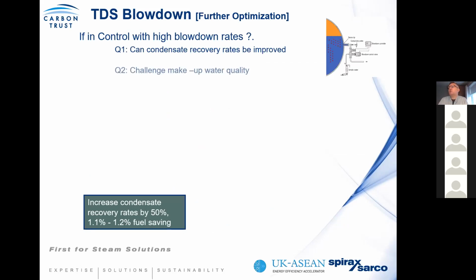Challenge makeup water quality. Just because you have soft water doesn't mean it's the best quality water for your process. Because again, soft water has impurities, and in your boiler, through evaporation, these impurities are retained in the boiler water, where the function of the TDS blowdown is to remove the impurities. So having a higher quality water means fewer impurities, which means less blowdown.